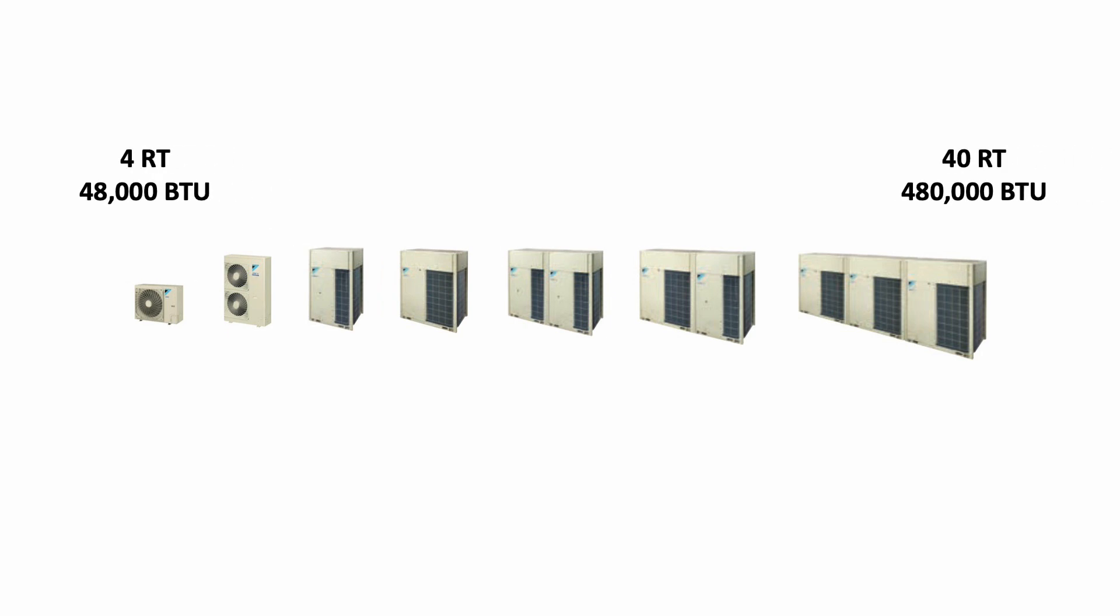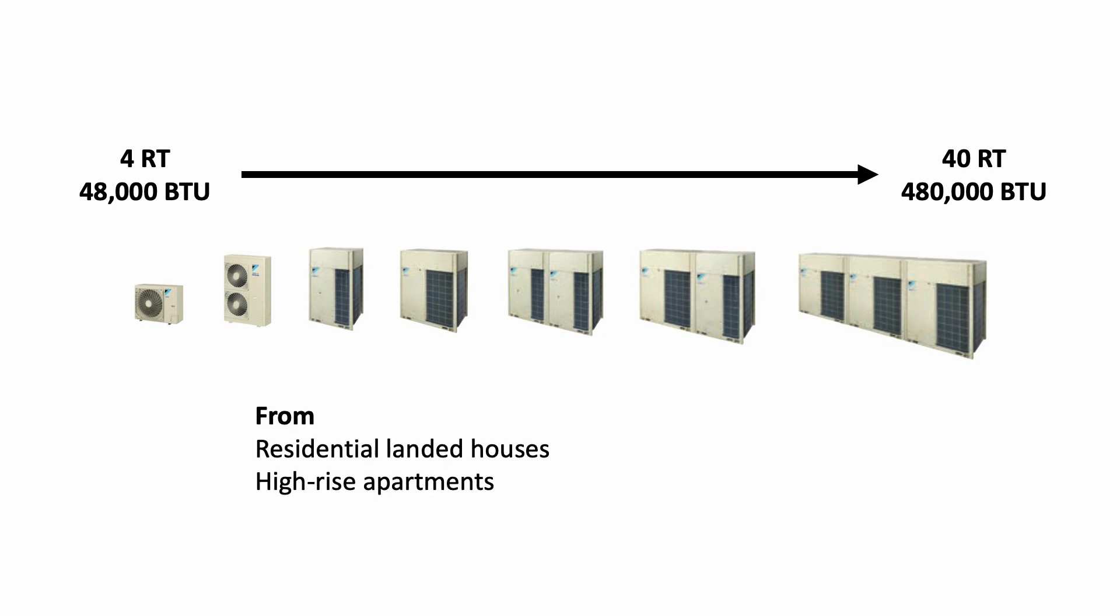Generally it starts from about four ton all the way until 40 ton. Some go higher, but I think the limit is somewhere there, 500,000 BTU. So the application for VRF system, the small one we can use at residential houses or even similar advantage as the multi-split, which is space saving. So those high rise apartments, we can use it.